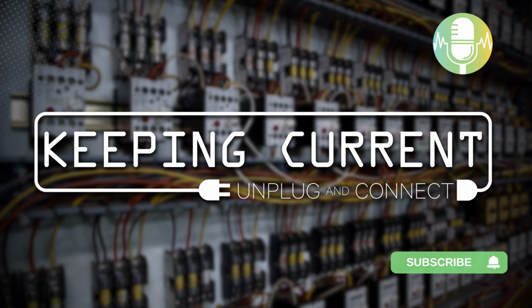Then we go into performance testing and commissioning - basically, let's put this through its paces. Let's charge fully, discharge fully, half charge. We do round trip efficiency testing, runtime testing, power quality meter testing, just to make sure that everything is working in the system.